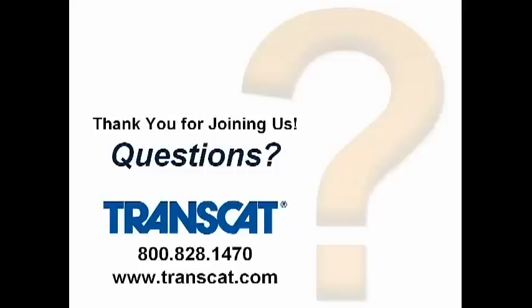We don't want to do that because if customers are trending their data, that would interrupt the trend. So if they have it in a control chart or something like that. So again, that's a client request to optimize. Otherwise, we adjust currently at 75% unless we're reporting uncertainties, and then we adjust when it's in the guard band. And that will likely be changing to adjustment in the guard band at any time. We're in the process of putting that into place.